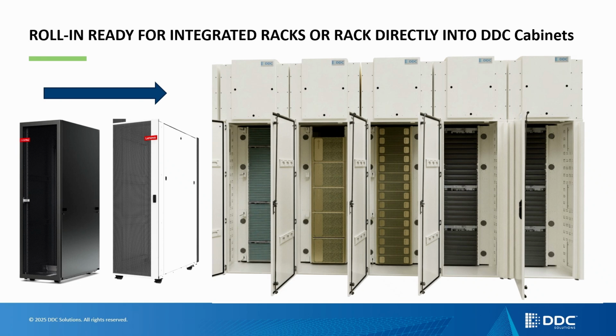While the cabinets you can see in the images have racks already built in them, so you can simply roll your equipment in and wire it up, a lot of folks are getting very specialized systems from folks like Supermicro, Dell, and NVIDIA, where it's already pre-racked. So the cabinets have a feature that allows you to roll an entire rack into the enclosure. You then put a grommet seal around the front of it, and you have all the cooling capabilities and flexibility of the DDC platform, but in a rack-ready roll-in capability.